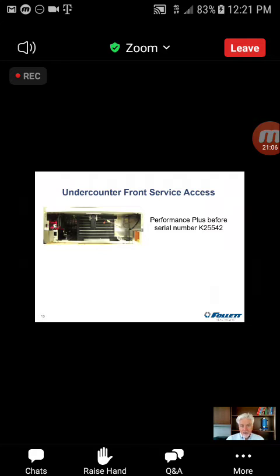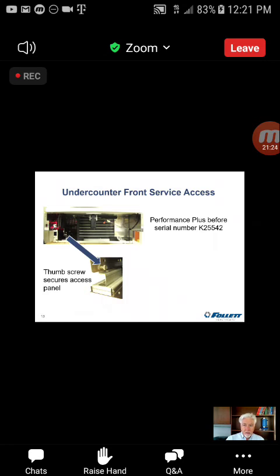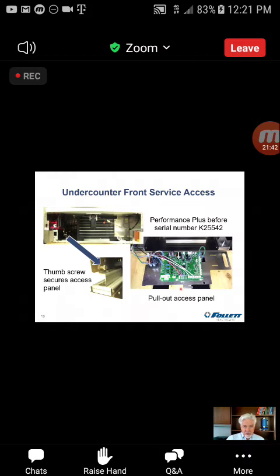Okay. So at that serial number, there were a few other changes as well, besides the way that the condensing unit is secured to the base of the unit when we pull it out from behind. The electrical box was different also. As you saw, the box on the serial number higher than this was mounted horizontally. Originally, it was mounted vertically on this plate that you kind of see right here. We'll be able to clarify that in just a moment. That plate is locked in place by the knurled screw that you see right here, or the thumb screw. So we need to loosen and remove that thumb screw, and then the whole plate gets pushed toward the back of the unit. Because as you can see, there's a hook on the bottom of that plate, and that locks into a bracket down here at the base of the unit.